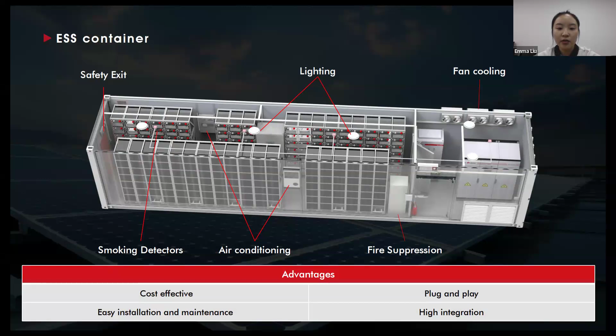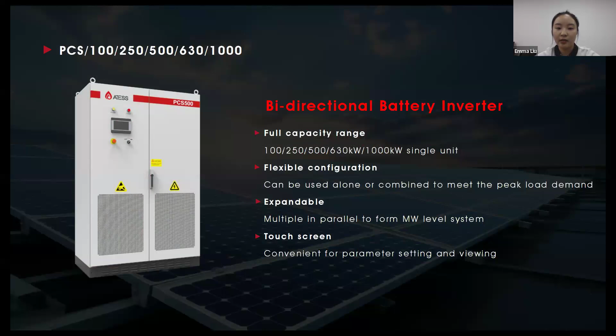The container solution we provide is equipped with AC, fire suppression systems, smoke sensors, and temperature sensors, so the safety of the system can be guaranteed. The PCS inverters we have applied for the two systems have 5 models, from 100 kilowatt to 1000 kilowatt single unit. And I can tell you the most popular models are actually PCS 500 and PCS 630. If there is an off-grid situation, up to 4 units can be connected in parallel. So we can do 4 megawatt max for off-grid.